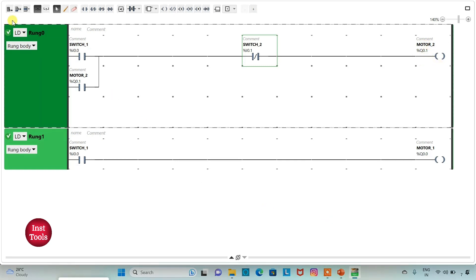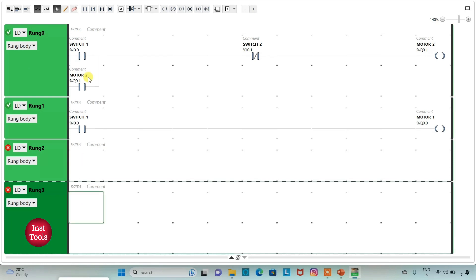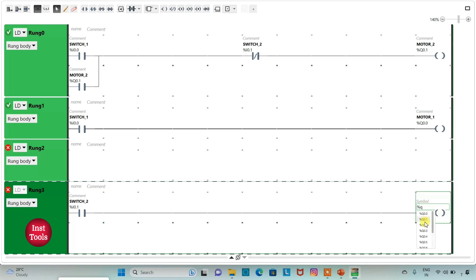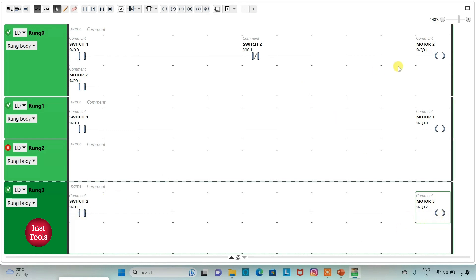Then I will add a new rung and insert a normally open contact and a coil. I will assign address I0.1 (switch 2) to the contact, and address Q0.2 with symbol 'motor 3' to the coil. So when switch 2 is on, motor 3 will be on and motor 2 will be off.